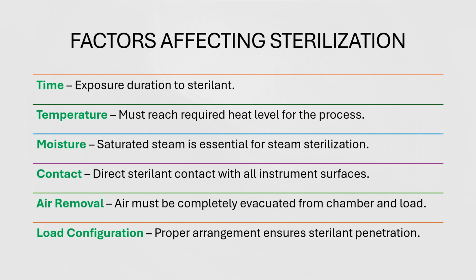The temperature must achieve and maintain the target temperature, and that is usually between 250 and 275, depending on what device is in the autoclave, and that also depends on what system we are using. Are we using a gravity or a prevac? Moisture. In steam sterilization, saturated steam is essential. Too much or too little moisture can compromise the results. If we have too much moisture, it's not going to dry effectively. The moisture is going to hang on to those devices. If it's too little, it's going to be superheated, so there are going to be more cold air pockets throughout the sterilization phase, and that's what we don't want.